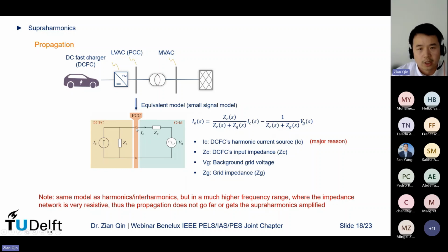So I would say the harmonic at the PCC point can only be lower than the harmonic emission from the charger or the background noise. So if you still see the problem, you should try to look into this one and that one, and try to reduce them. That is the way to go.